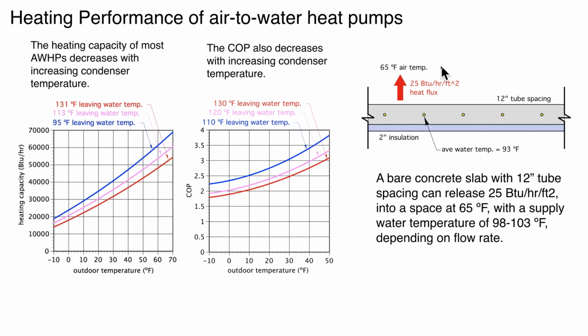So all this would require is an average water temperature of 93 degrees Fahrenheit. And 25 BTUs per hour per square foot is for a reasonably insulated building; certainly we can get that load lower with more insulation. You can see we're at bathtub temperature water. Supply water temperatures vary from maybe 98 to a little over 100 degrees at design load, and then we can use outdoor reset control to bring that water temperature even lower. So again, we've got a nice match between the water temperature requirements of that bare slab and the conditions that give good performance on the air-to-water heat pump.